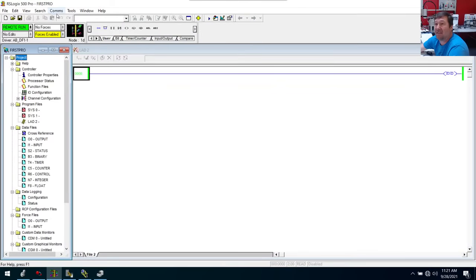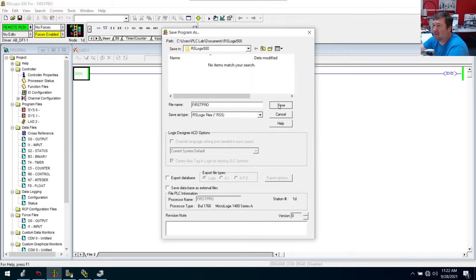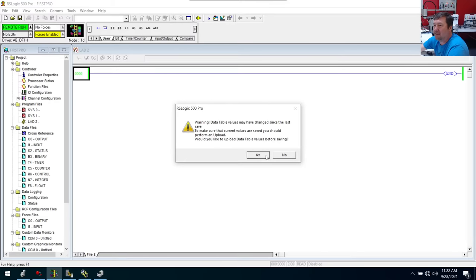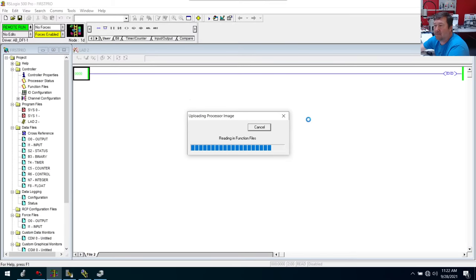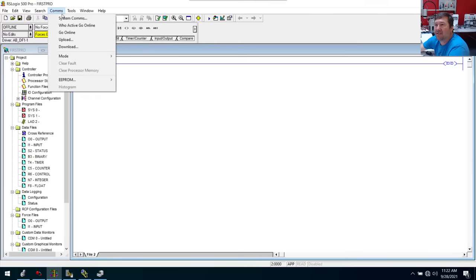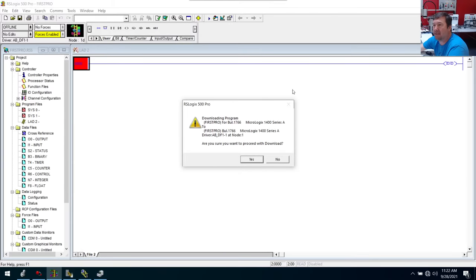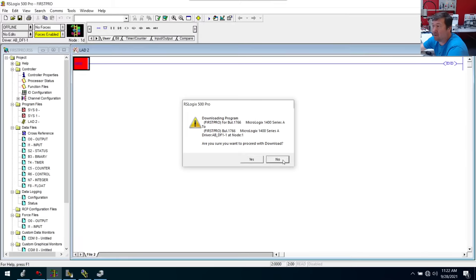I'm going to go offline with this one. We're going to save our changes. We'll upload the processor image. And then now we're offline. I'm going to go to Communications and system communication — we found our PLC and we're going to hit the download button. We think we want to download our program from the PLC. It says downloading program, and it's telling you about the PLC over this driver. Are you sure you want to proceed with download? Pay attention to this and make sure you know what you want to do. Unfortunately, you'll probably learn the hard way: if you download, you're going to overwrite your program.